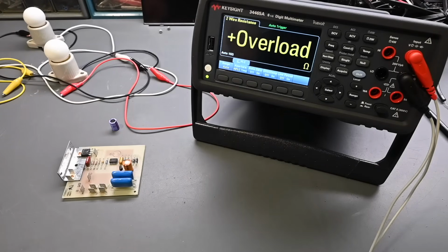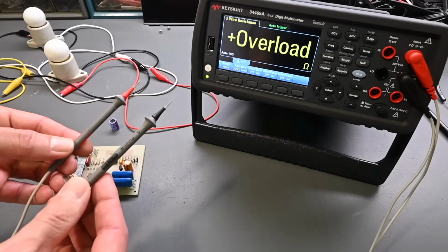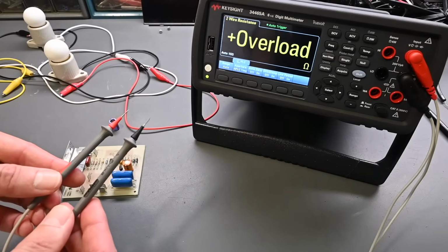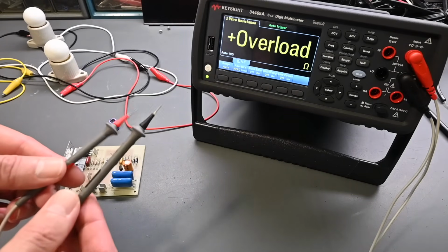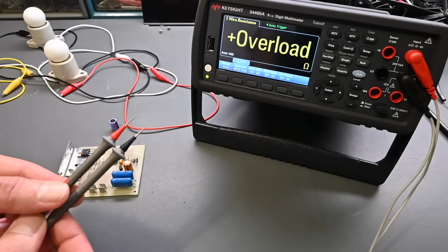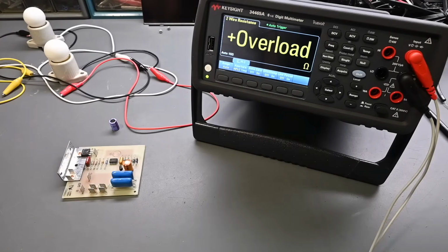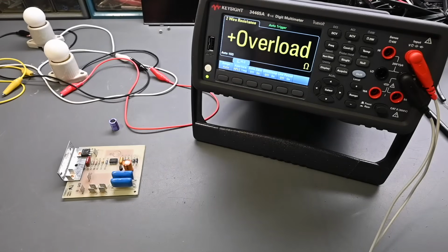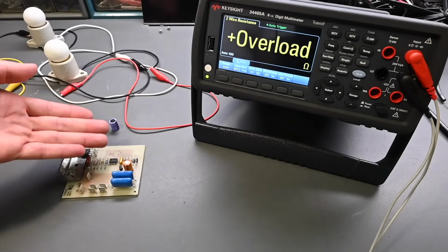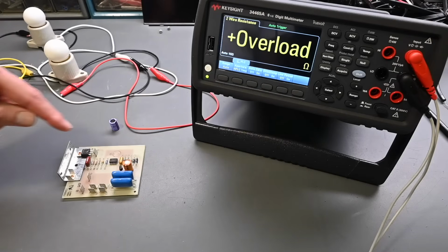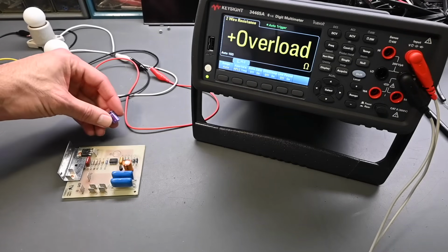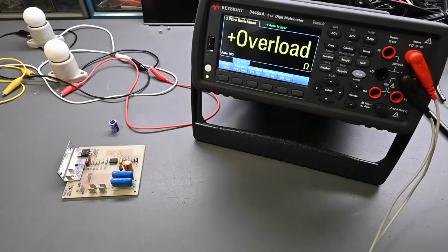The reason is there's some current that has to flow out of the test leads. This is basically like a small power supply when used in resistance mode, and that voltage causes a current to flow into the capacitor, charging it up. You get fluctuating measurements, with the resistance value drifting all over the place as the capacitor tries to charge up. You'll still see that effect with some remaining capacitors, but not to the extent this one was causing.